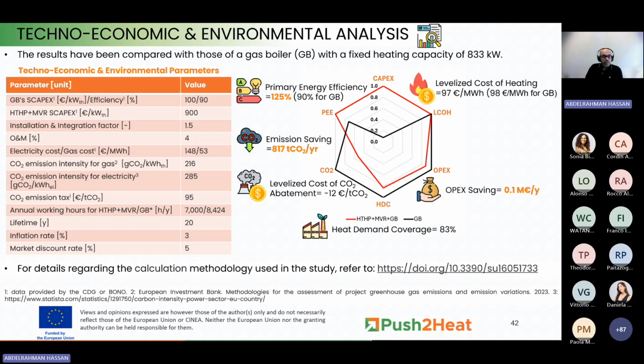Annual working condition, as I have mentioned, 7,000 hours. And on the other side, the gas boiler will work almost the whole year, 8,424 hours per year. The expected lifetime is 20 years. Inflation rate 3 and discount rate is 5. So based on this data, you can see here in the radar diagram the comparison between our system in red, the proposed system, high temperature heat pump plus mechanical vapor compression, and gas boiler as a backup boiler to cover the deficit in the annual working hours.